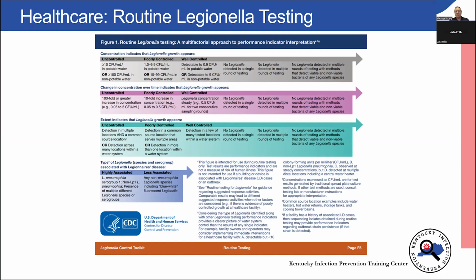The second half, or the lower part of that gray bar that says "or," is for non-potable water, which is your cooling towers. For your non-potable water, they list uncontrolled as above 100 CFU, and anything from 10 to 100 is poorly controlled. For cooling towers and for non-potable sources, most laboratories will use the limit of detection as 10, so they really won't be reporting anything less than 10. It can be done; you just need to ask your laboratory. In Europe, sometimes they go down to 1 even for cooling towers. But if you're below 10, the CDC is looking at it as controlled.